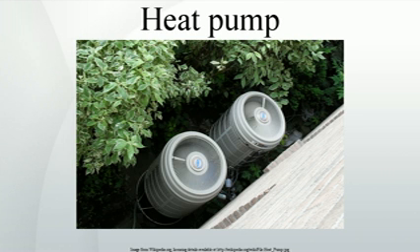Geothermal heat pumps or ground source heat pumps use shallow underground heat exchangers as a heat source or sink, and water as the heat transport medium. This is possible because below ground level, the temperature is relatively constant across the seasons, and the earth can provide or absorb a large amount of heat. Ground source heat pumps work in the same way as air source heat pumps, but exchange heat with the ground via water pumped through pipes in the ground.